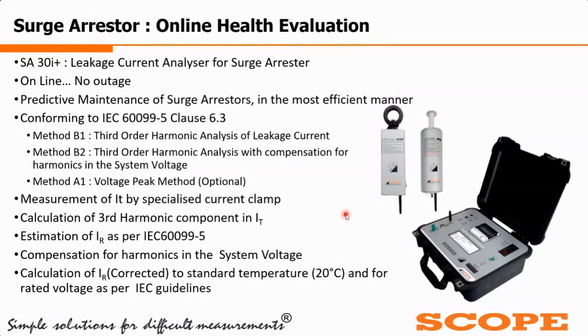And in case of some zones where we are not in a position to put this field probe, we may have to use the A1 method, which is called the voltage peak method. This is an optional feature of this kit and is not supplied by default as a standard feature. So if you make an additional request at the time of purchase that the voltage peak method is required, then some other accessories will come along with the kit, and the same kit will be activated in the software menu with method A1. Then this kit can be used for the A1 method also. So maximum this kit can work on 3 methods.